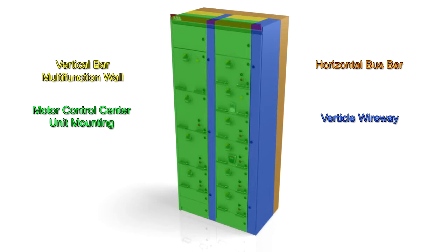For maximum operator safety, the horizontal busbar is fully segregated from the front accessible areas of the motor control center. The vertical busbar's insulating and isolating design provides IP20 touch safe protection.